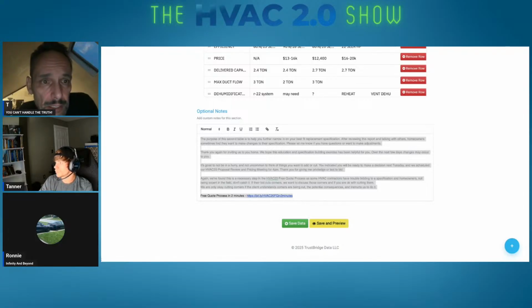The biggest problem we are seeing is equipment that is oversized to the ductwork. Since 2019, for optimum equipment performance and longevity, sizing to ductwork has become more important than sizing to house load. If you have no intention of replacing ductwork, we recommend sizing to the left of the red insufficient duct hash mark. If on the hottest or coldest days your thermostat slides a degree or two, we can discuss home improvement measures that will improve your comfort.